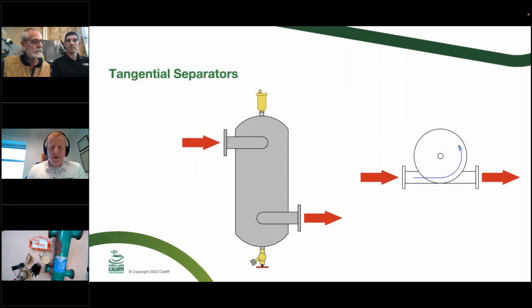Yeah, we actually had a great comment come in. Do we require straight pipe for the newer style coalescing type air separators? You want to take that one on, Bob? No, you can put those right up against the fitting, an elbow, a T, whatever you might have. And a question that came in also relates to that: on which side of the pump should it go? It can go on either side of the pump. We want the air separator, like Cody said, at the hottest point in the system. So the closest you can get it to the boiler, or on the outlet side of a return side of a chiller where the water is coming back warmer, that's the best spot for it.